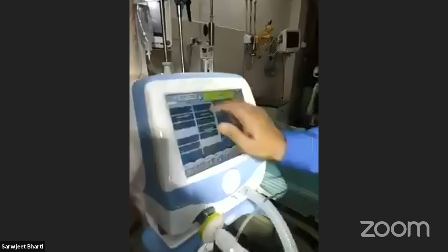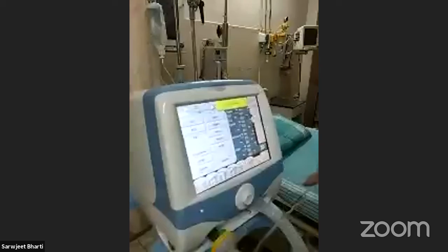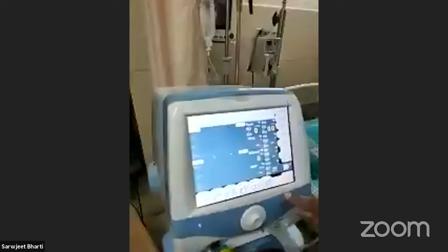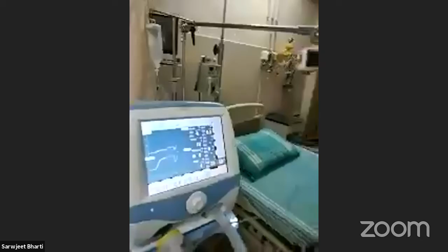What options do you have in the ventilator? We have the option to use straight away PSV itself. We have the pressure support ventilation option. We can use that. This is the option we have. And if you see, I'm tightening the limb to prevent the leak from the mechanical PEEP valve. So now if you see, it is getting ventilated with straight away pressure support ventilation. I can see intermittently the bubble going up and down. So this is one option you have.